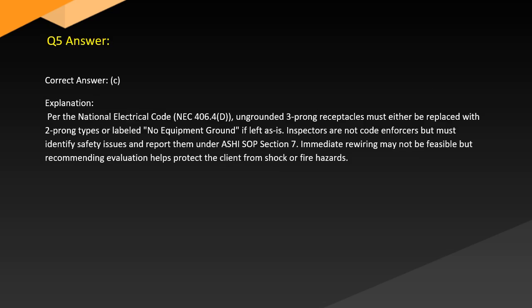Answer. Correct answer: C. Explanation. Per the National Electrical Code, NEC 406.4(D), ungrounded three-prong receptacles must either be replaced with two-prong types or labeled "No equipment ground" if left as is. Inspectors are not code enforcers, but must identify safety issues and report them under ASHI SOP Section 7. Immediate rewiring may not be feasible, but recommending evaluation helps protect the client from shock or fire hazards.